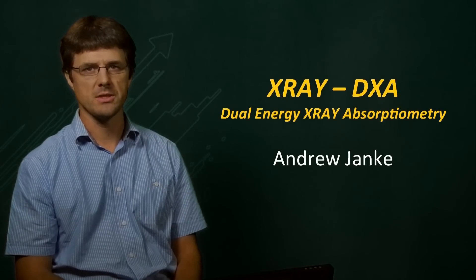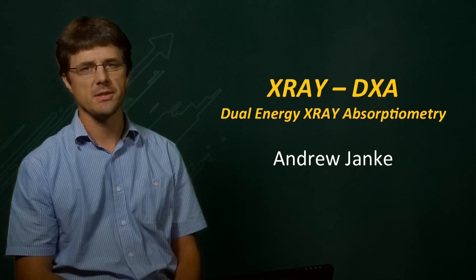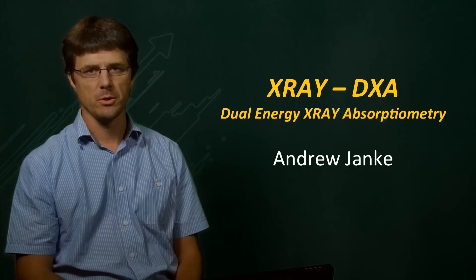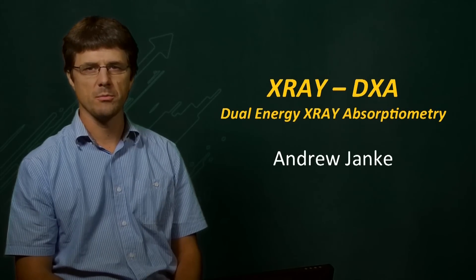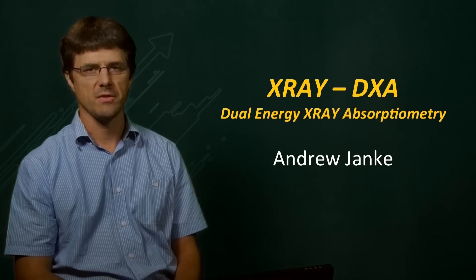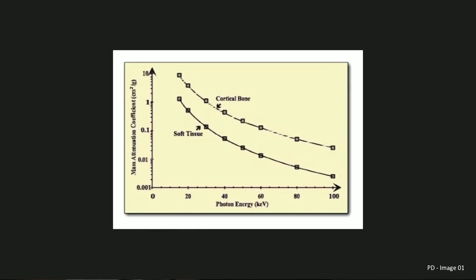X-rays penetrate body tissue at differing rates depending upon their intensity. Techniques such as DXA or DEXA exploit this phenomenon and use subtraction of multiple scans to obtain estimates of bone mineral density and fat content. DXA, or Dual Energy X-ray Absorptiometry, uses two X-ray images of different energy. A soft tissue absorption image is subtracted from a higher energy bone image in order to estimate bone density to a high degree of accuracy.